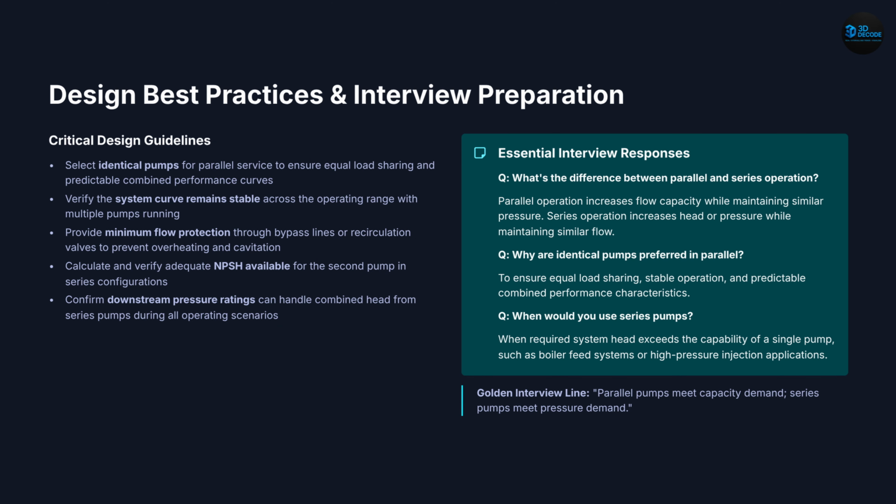Slide 14. Design best practices. For parallel systems, always use identical pumps for stable operation. Ensure proper minimum flow protection. For series systems, verify NPSH and pressure limits. Always check system curve interaction.